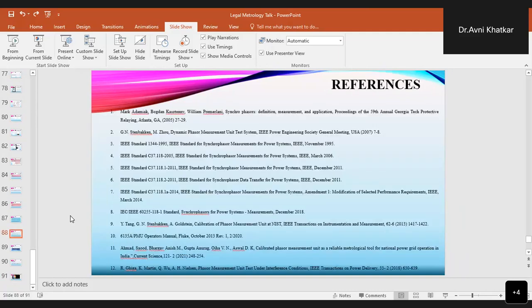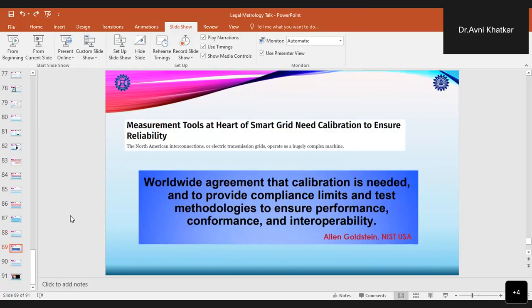These are various references which are being used. The North American interconnections, the electrical transmission grid, which operates as a hugely complex machine, also say that measurement tools at the heart of the smart grid need calibration in order to ensure reliability. And Allen Goldstein, who works on PMUs at NIST USA, stated that there is worldwide agreement that calibration is needed, and that compliance limits and test methodologies are required to ensure performance, conformance, and interoperability.